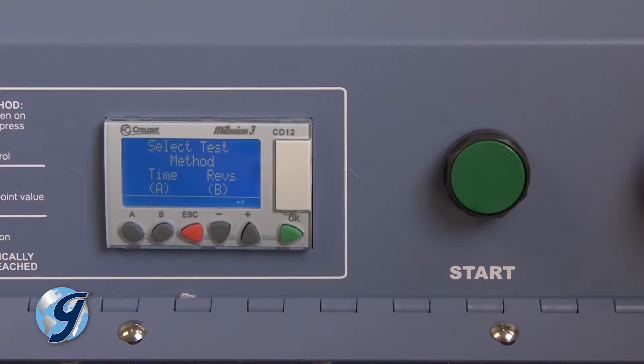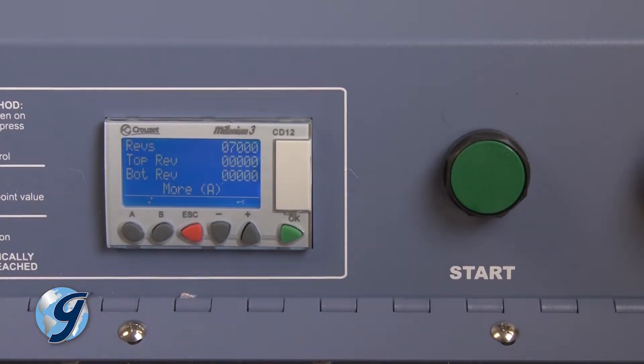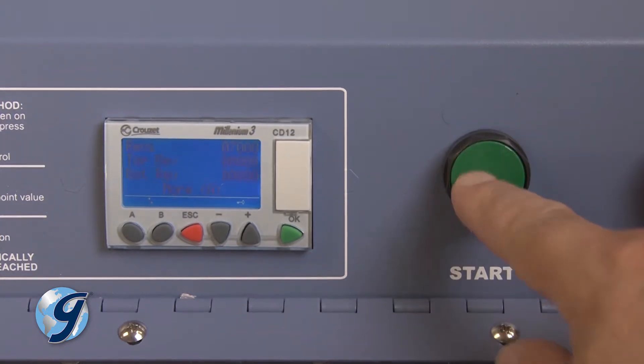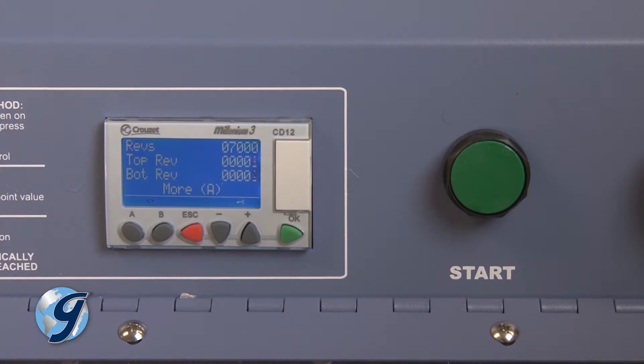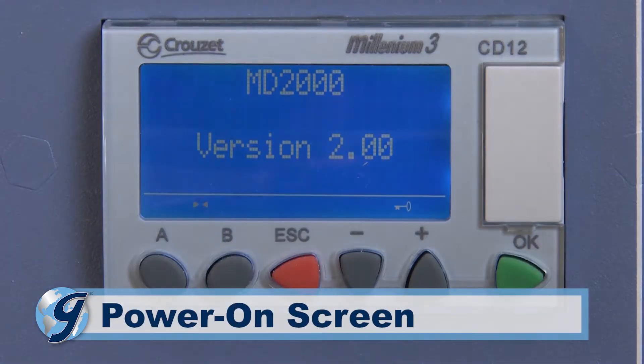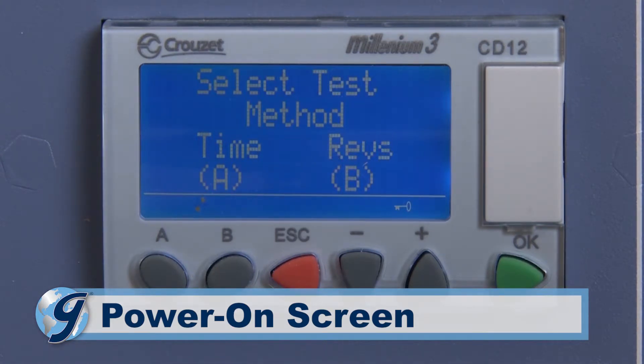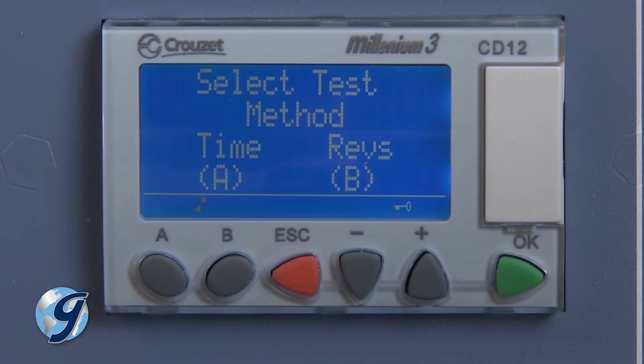If the desired test operational mode and value is already displayed, the test may be started immediately by pressing the green start button. When the MD-2000 first powers up, the user is prompted to select either time or revolution mode. Press A for time mode or press B for revolution mode.